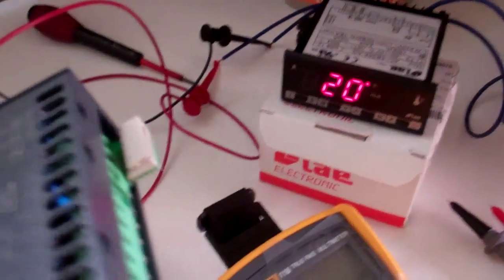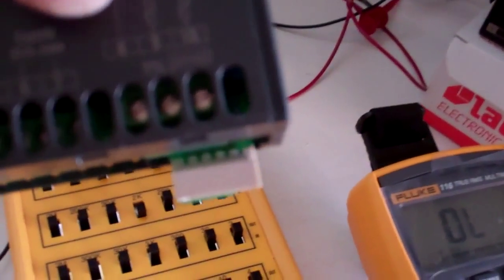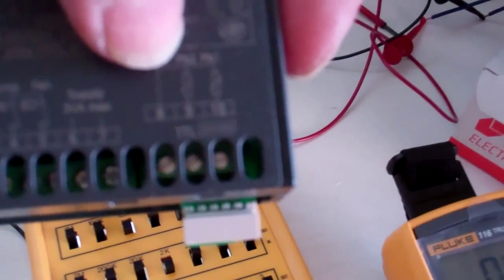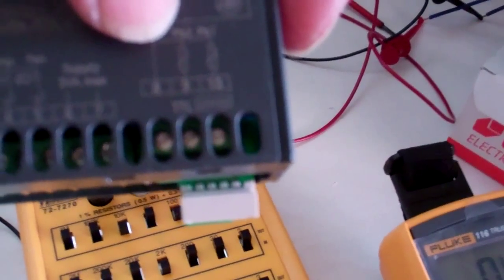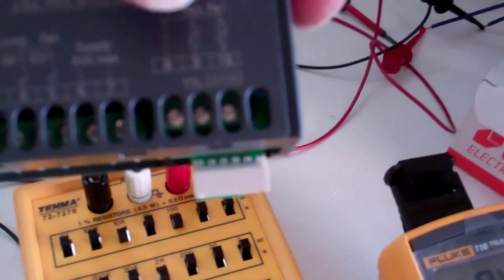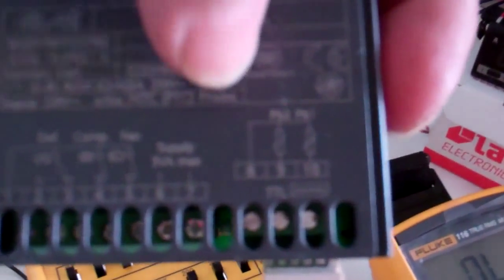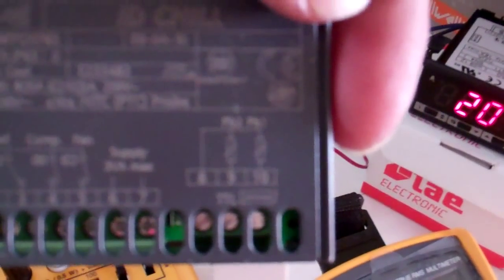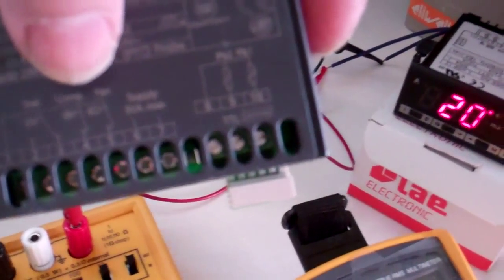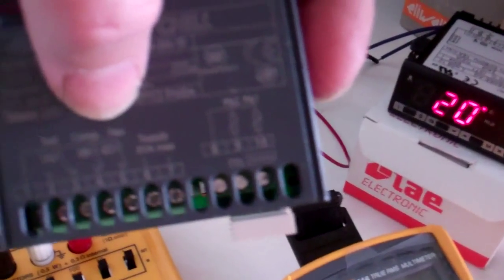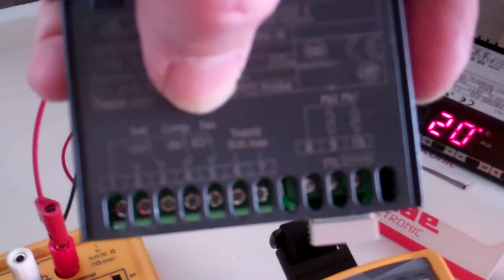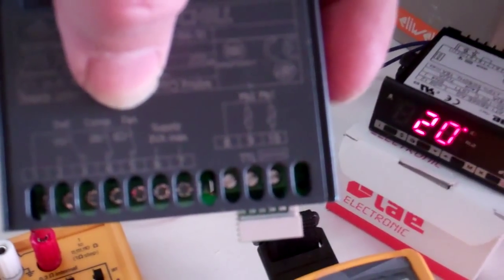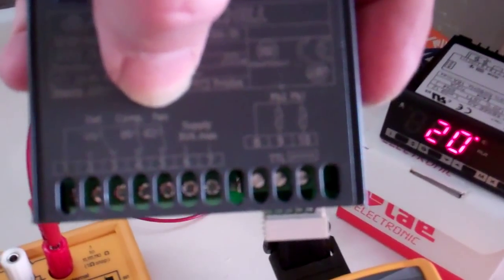Some have two probe inputs, this has got two, some only have one, depends what they're doing. Second probe is usually in the evaporator to tell if it's iced up so it knows when to start and stop a defrost or even start the fan up if it only brings the fan on once the evaporator is cold again.